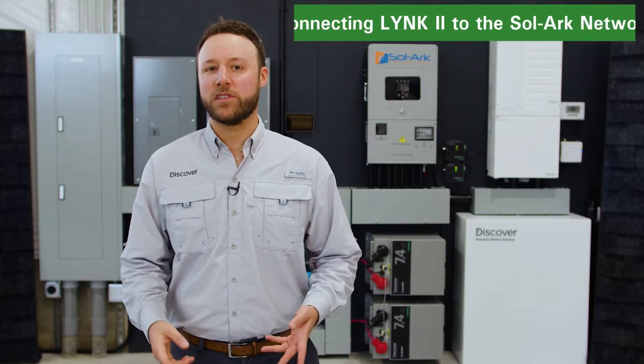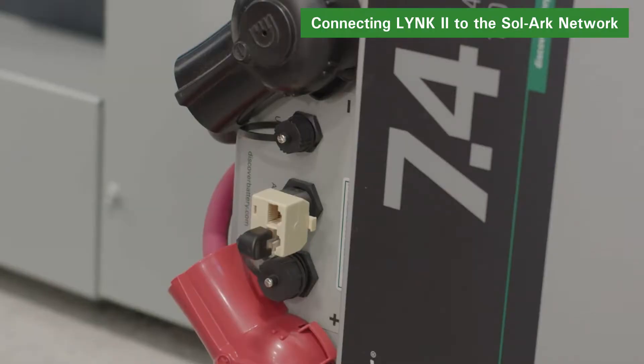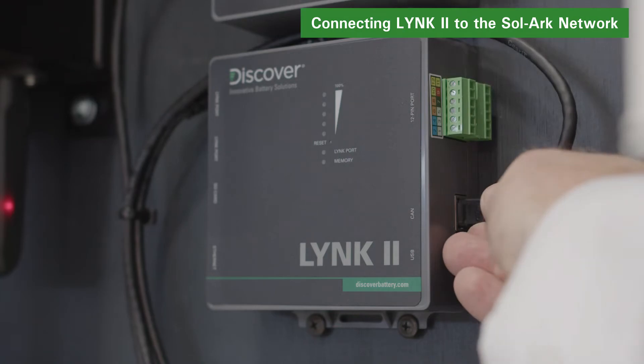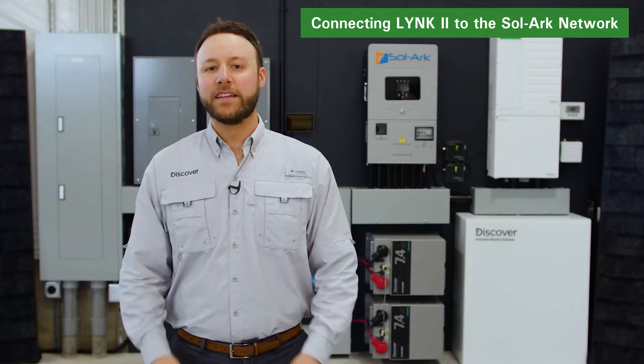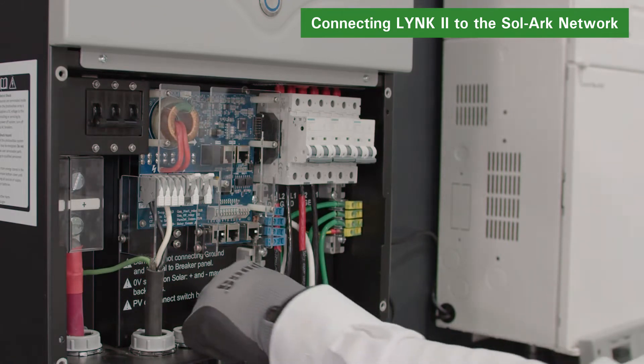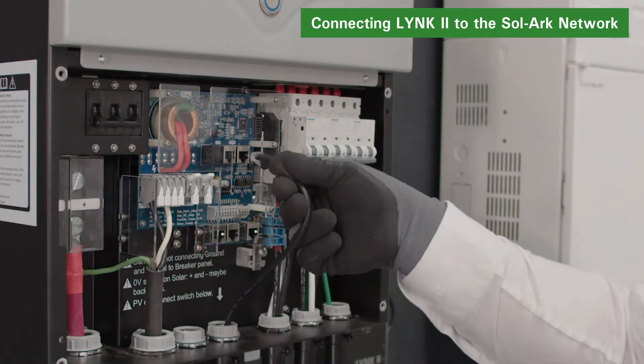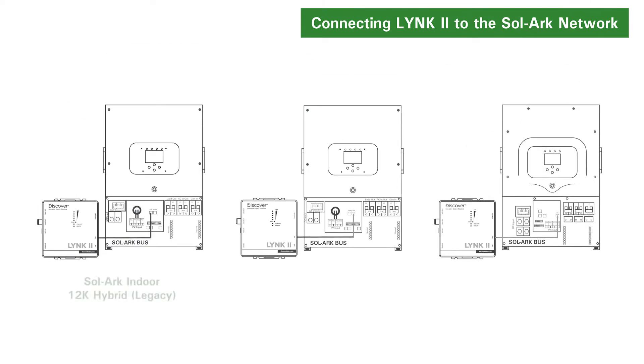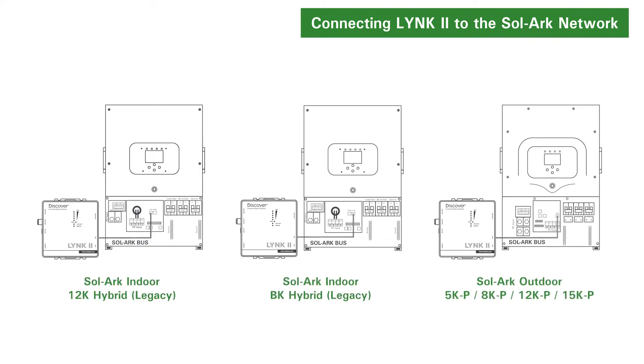Once the CAN-OUT pins of the LYNK II are correctly configured, the Discover Lithium battery can be connected to the LYNK II using a CAT5 cable. After connecting the batteries to the LYNK gateway, connect it to the Sol-Ark inverter using a CAT5 cable inserted into the correct CAN port. Note that the CAN ports are in different locations on the Sol-Ark inverter depending on the model.